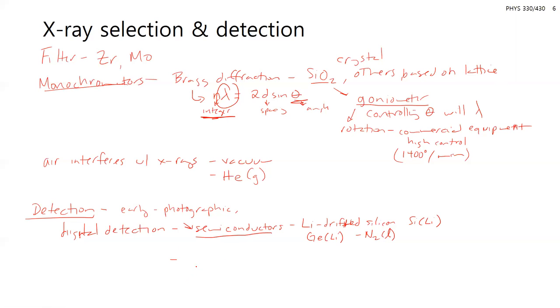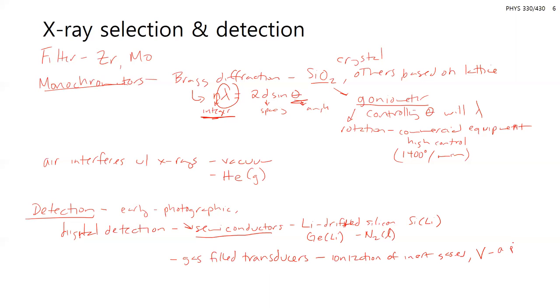Some other x-ray detectors that are not photographic include gas-filled transducers. When x-rays hit the gas within the detector, it causes ionization. These are typically inert gases — the right-hand side of the periodic table, argon, xenon, and the like. Once those gases are ionized — the x-rays are high energy enough to kick off one of those inner shell electrons — you have a charged gas, then you detect the potential produced by those charges. The voltage has to be amplified and is then electronically detected.